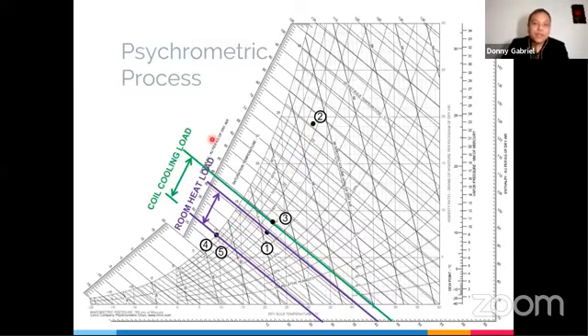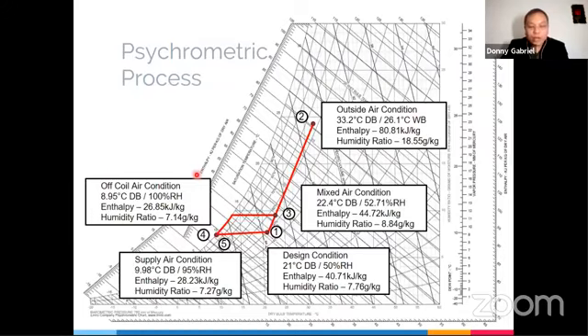So you can see here, previously the coil load is from here to here. Now it's just from here to here. So the change in enthalpy is significantly less. So what is our coil load? So from here to here, can you guys calculate what is the change? What is the coil load needed now? So assuming at 24,000 cubic meter per hour, what is the coil load needed for 3 to 5?